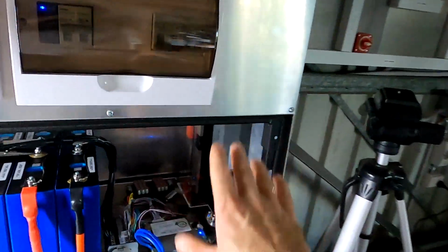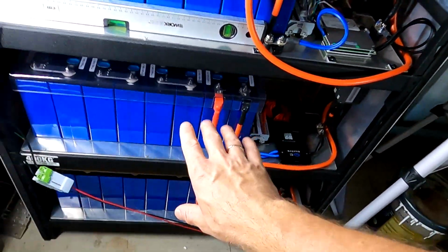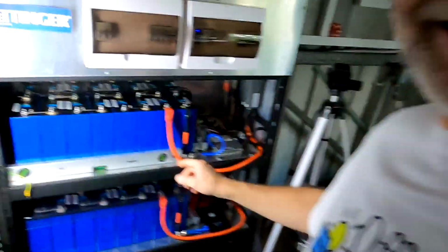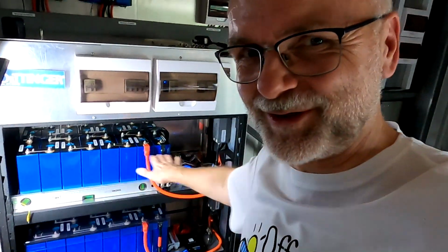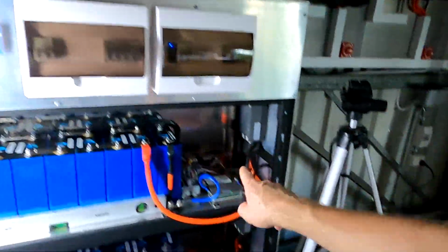This is all the inrush current you get when you reconnect the battery bank to your system. The voltage has not changed. Even the other ones have charged all the time, and this one hasn't - again, flat area of the curve. There you can see it again.